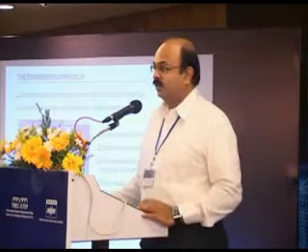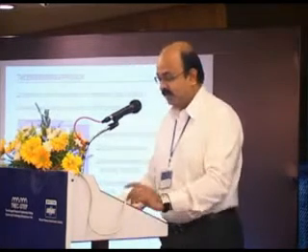And so you can do some instrumentation. Sometimes you don't know certain things, so you can identify some locations where you monitor the temperature from now on. You are in doubt now, so you can additionally add some metal temperature thermocouples, and you have to monitor, inspect them, and then confirm that the predicted behavior is being achieved, and then you have made a reasonably good conclusion. So you can add instrumentation to help you arrive at the solution.